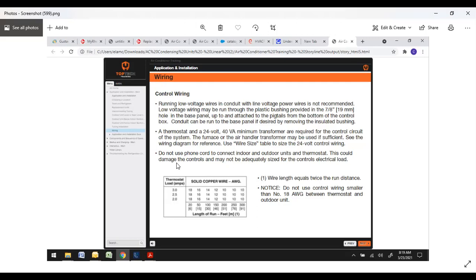Wire size, this is big. Don't use phone cord to connect indoor and outdoor units. Don't use phone cord or speaker wire. There's all kinds of funny little thin wires out there. This could damage the controls and may not be adequately sized for the control electrical load. So use 18 gauge, which is what's recommended between the thermostat and outdoor unit.